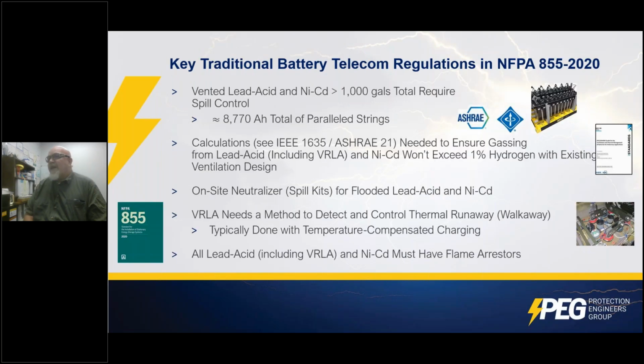Here are some traditional battery telecom regulations in the 2020 edition. If you have more than 1,000 gallons of electrolyte total, you require spill control. That's actually a lot of batteries: 8,770 amp hours at 48 volts. You have to do calculations, and you can get them from the manufacturer, done per IEEE 1635/ASHRAE 21, and that includes VRLA. VRLAs are not sealed batteries.